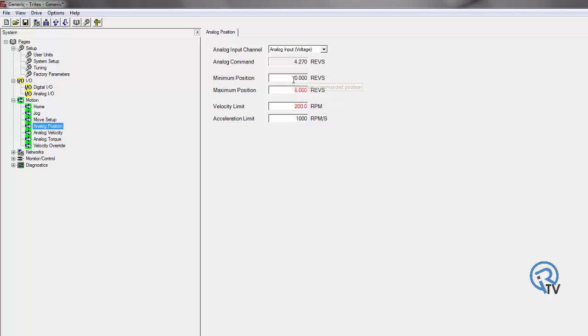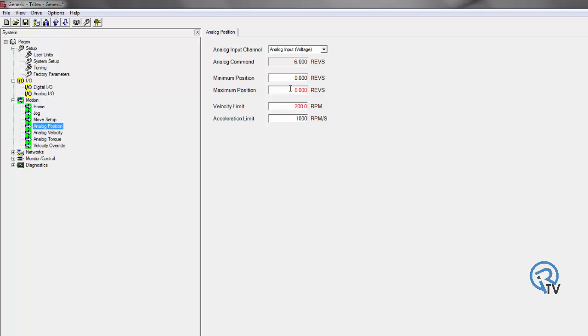For this example, I have it set up as my minimum position or 0 volt signal from analog reference. I'm going to go 0 revs. My 10 volt signal from my potentiometer is going to give me 6 revs, and I'm going to go velocity of 200.